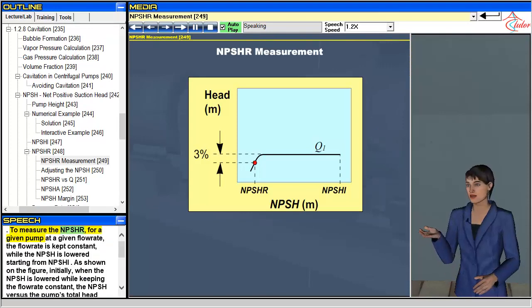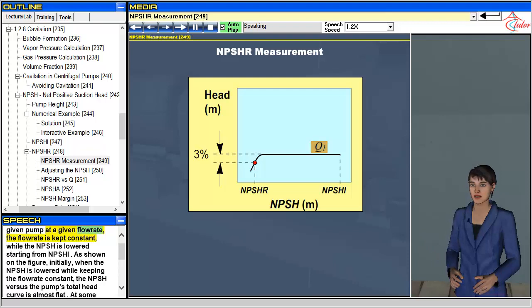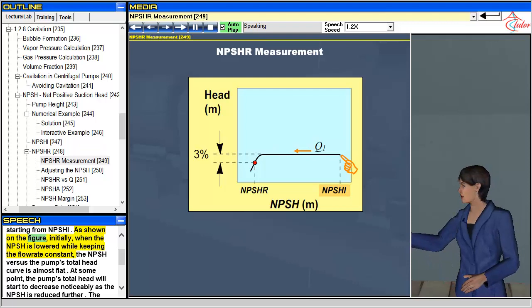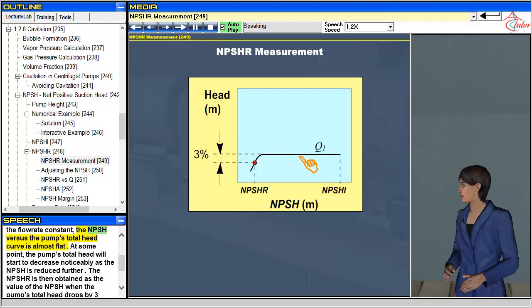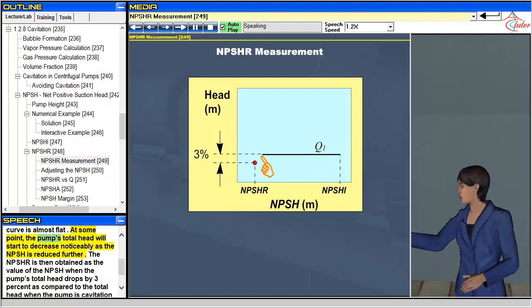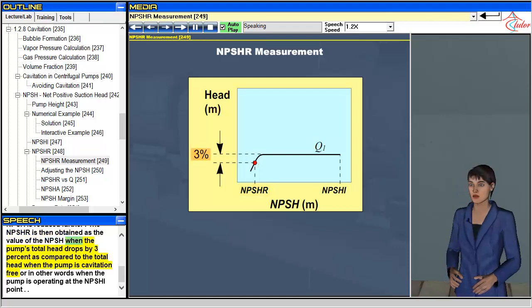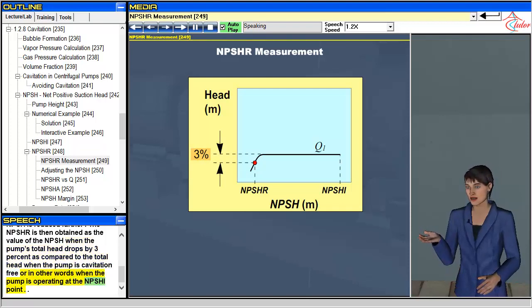To measure the NPSHR for a given pump at a given flow rate, the flow rate is kept constant while the NPSH is lowered starting from NPSHI. As shown on the figure, initially when the NPSH is lowered while keeping the flow rate constant, the NPSH versus the pump's total head curve is almost flat. At some point, the pump's total head will start to decrease noticeably. The NPSHR is then obtained as the value of the NPSH when the pump's total head drops by 3% compared to the total head when the pump is cavitation-free, i.e., operating at the NPSHI point.